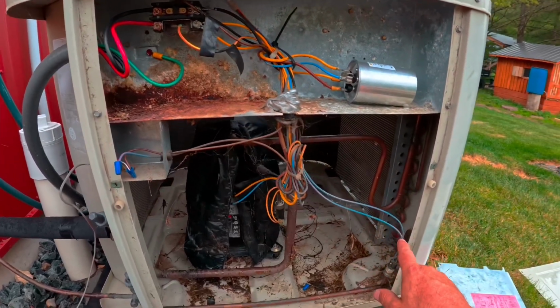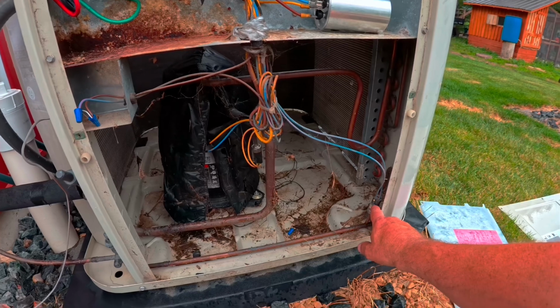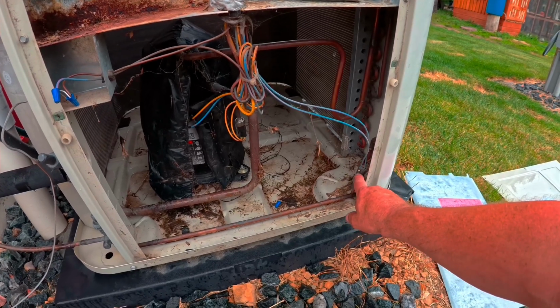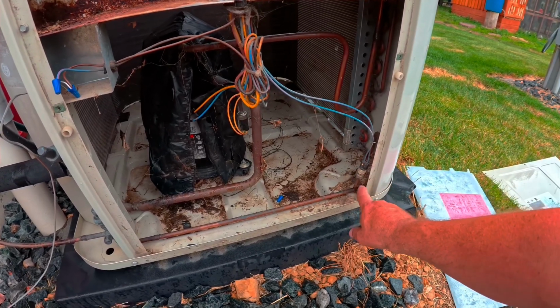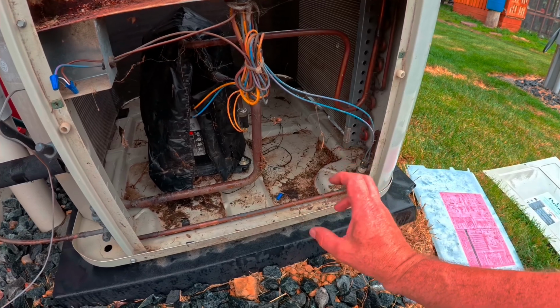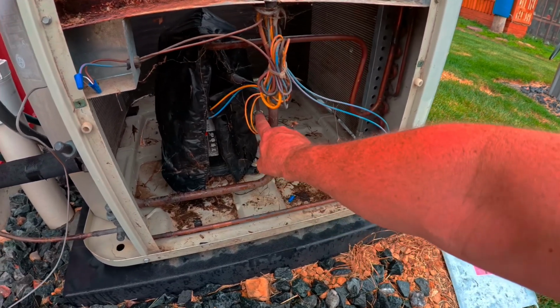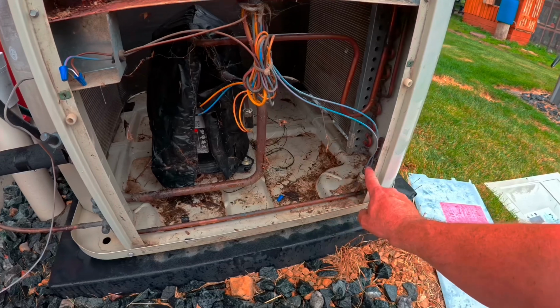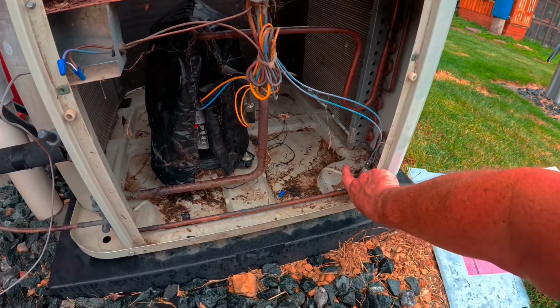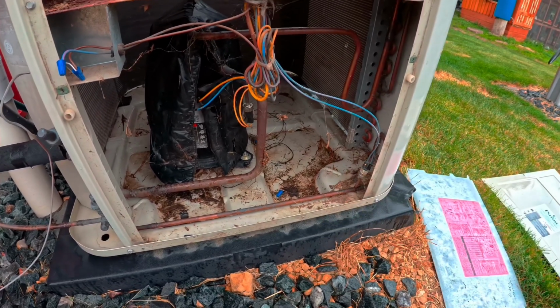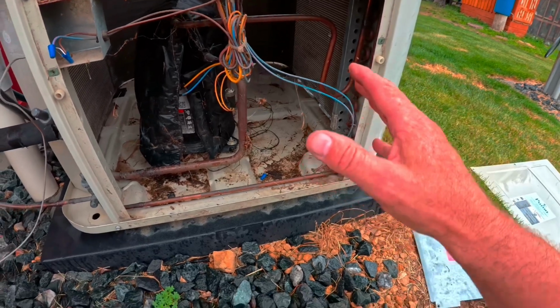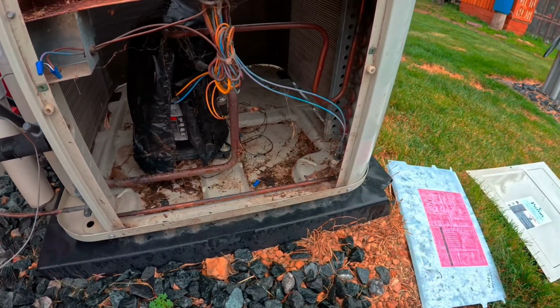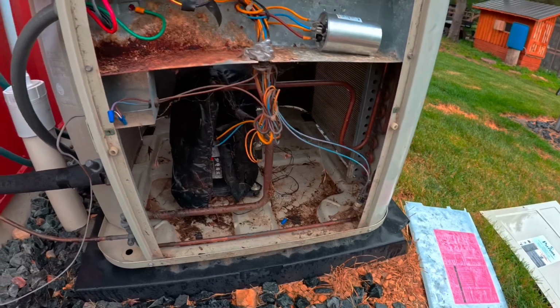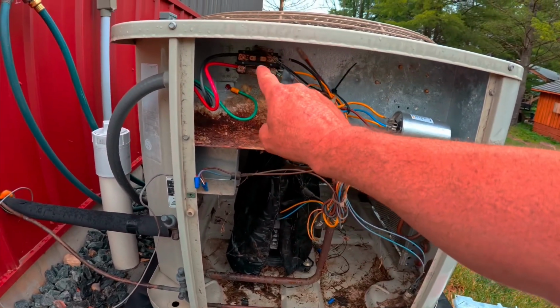So now we need to go backwards and check these switches here. Now on my system, these are automatic reset switches. So if it trips on high pressure, when the pressure resolves, it'll close back. Same thing with the low pressure. Some high pressure switches have a mechanical button you need to actually manually reset. These are automatic resets, so again, we know that's not the situation. Most common problem is the contactor failing.